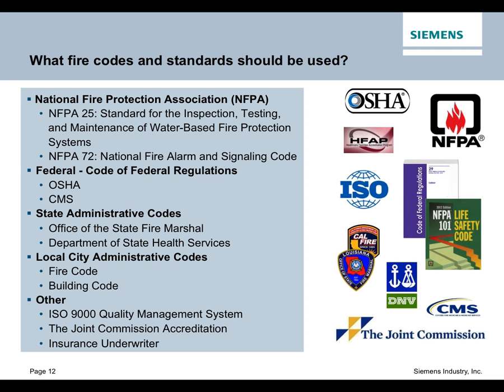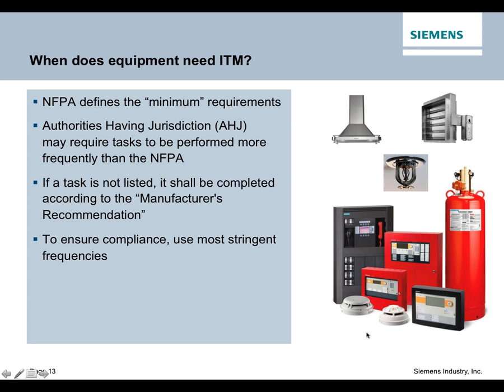There are a couple of other areas here. The ISO folks, that's a quality management system that companies and organizations get rated by. They have their set of standards. We mentioned the Joint Commission. They're connected with the CMS. That's all part of the healthcare world. And then, of course, your insurance underwriter. Most insurance companies rely on NFPA, but once again, not all. The folks within Factory Mutual, FM, they write their own standards. Once again, they are very similar to NFPA, but sometimes, based on their own risk analysis, they'll make changes and say, we've got to follow these specific requirements in the FM approval guide. So it's a matter of just knowing where we need to go, because things can be different and fluctuating.